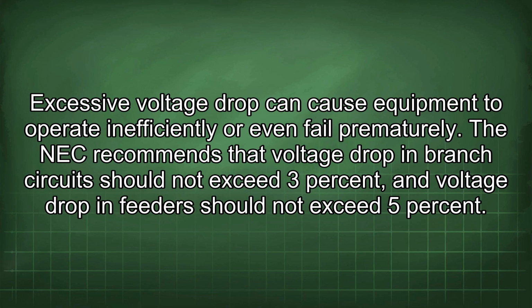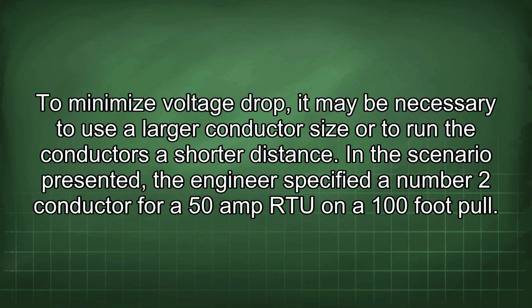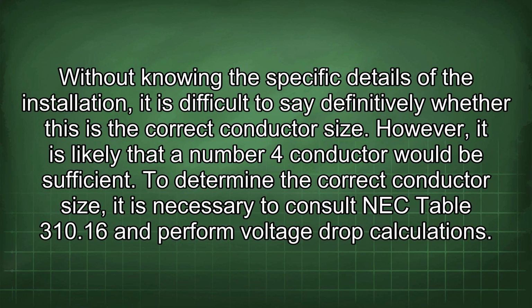The NEC recommends that voltage drop in branch circuits should not exceed 3%, and voltage drop in feeders should not exceed 5%. To minimize voltage drop, it may be necessary to use a larger conductor size or to run the conductors a shorter distance. In the scenario presented, the engineer specified a number 2 conductor for a 50 amp RTU on a 100-foot pull. Without knowing the specific details of the installation, it is difficult to say definitively whether this is the correct conductor size.